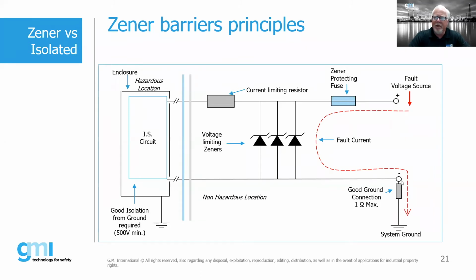Now notice here, and this is the important thing to note on the right-hand side, with Zener diodes, it's imperative that we have a good, dedicated system ground that is separate from our normal ground. This is called our clean earth, as opposed to just our standard earth. Our requirements on our ground for our system earth for IS requires 1 ohm resistance or less. It's a very, very small amount. But basically, this is critical and important when we're using Zener diode type products.